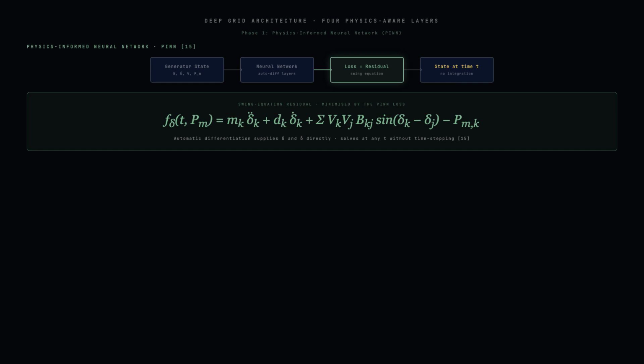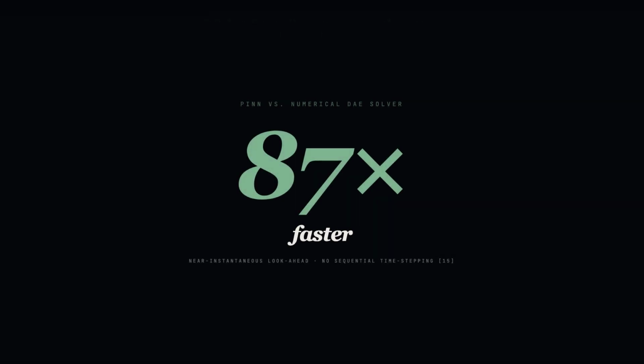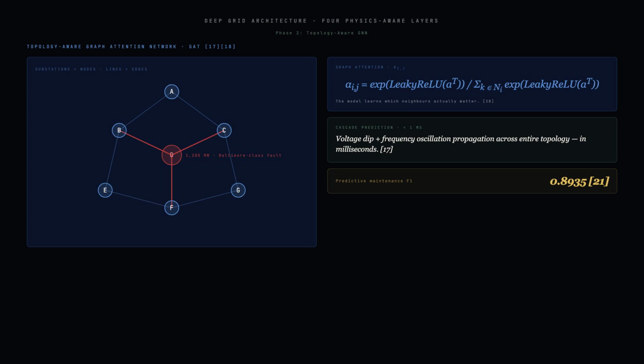It is a physics-aware engine built in 4 interlocking layers. The first layer is physics-informed neural networks, or PINNs. Unlike standard neural networks that learn only from data, PINNs embed the laws of the system directly into their loss function. For generator k, the network is trained to minimize the residual of the swing equation: M_k times delta double dot plus d_k times delta dot plus the network sum of voltage terms times the sine of the rotor angle difference, minus the mechanical power input. By using automatic differentiation to compute the velocity and acceleration of the rotor angle, the PINN determines system states up to 87 times faster than conventional numerical solvers and at any specific time t without sequential time stepping. Look-ahead during a potential blackout becomes near instantaneous.